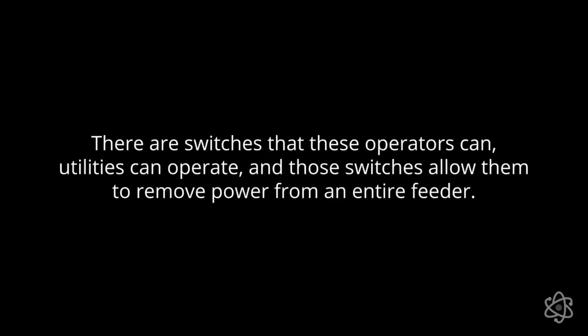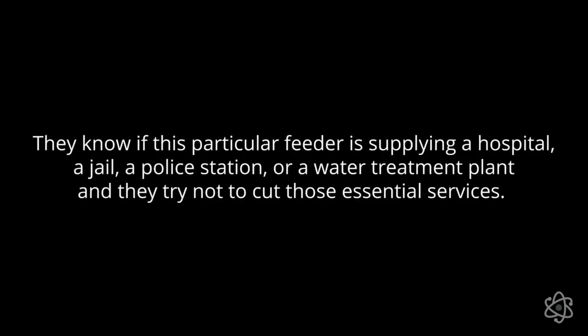There are switches that these operators, utilities can operate. And those switches allow them to remove power from an entire feeder. And in doing that, leaving unfortunately thousands of people without power, but it allows them to quickly bring down demand to help demand meet supply. So they know if this particular feeder is supplying a hospital, a jail, a police station, or a water treatment plant. And they try not to cut those essential services. And so in general, if you are less lucky in some ways and you're not living close to any of these facilities, you're more likely that in a decision like this, your power will be cut down.